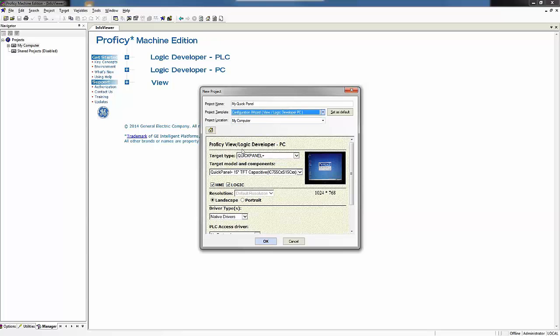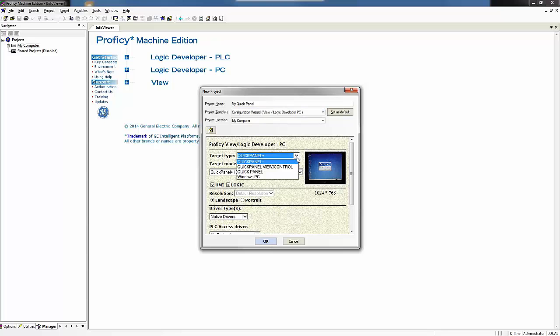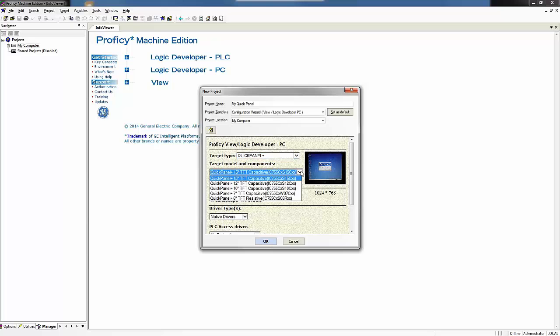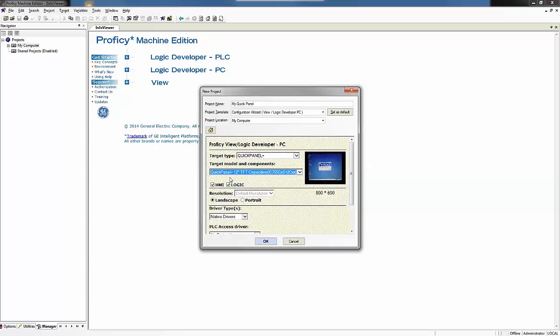When I pop that up I get my configuration wizard here below me. First up is target type. You see I have a QuickPanel plus but there's other options for QuickPanel view slash control or regular QuickPanel. We have the QuickPanel plus and I happen to have not the 15 inch that comes up by default but I have the 12 inch QuickPanel plus. And I'm choosing to use just the HMI portion of it. The QuickPanel plus can also be a controller with logic but I'm going to uncheck the logic so it doesn't add that.